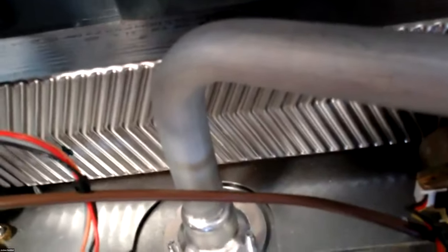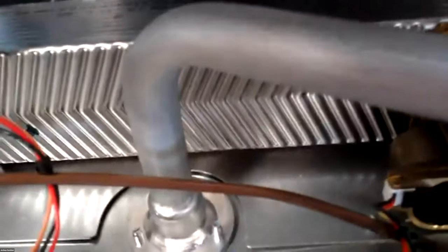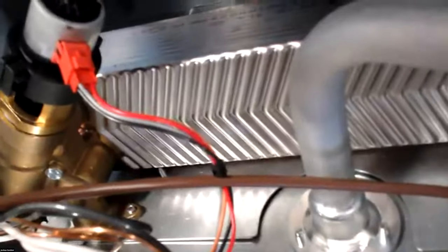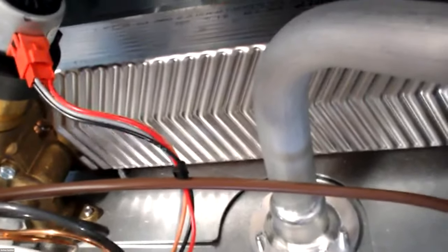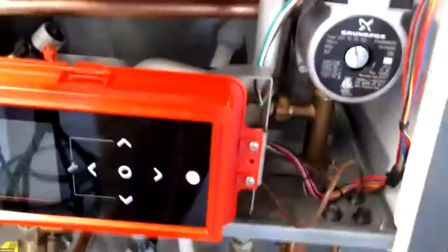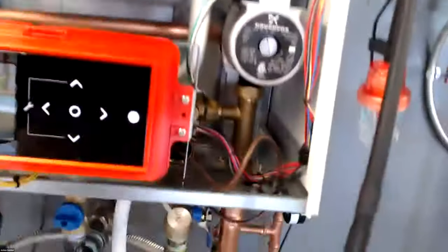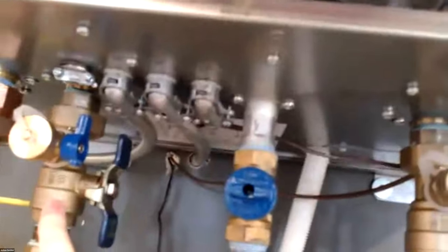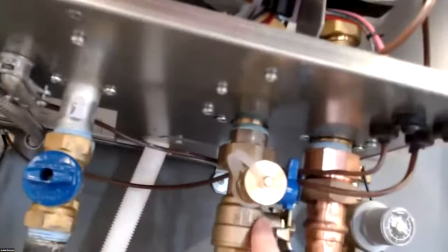Opposed to some manufacturers that are up in the 180s, they're actually running about 88% efficient on their domestic. So we're getting that high output on our domestic, and we're still achieving 90% efficiency on the output, which is really nice. On the flat plate, there are two T20 Torx screws that remove it. So you can absolutely put blow down drain valves to flush out the flat plate heat exchanger.